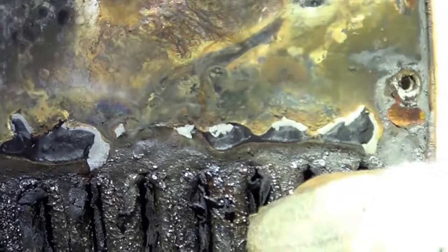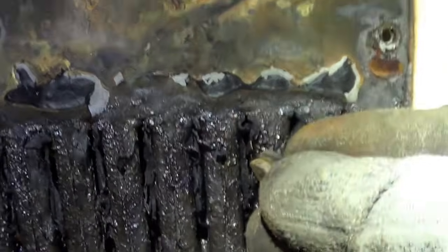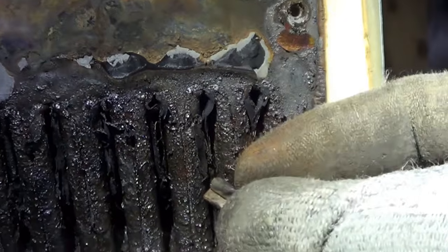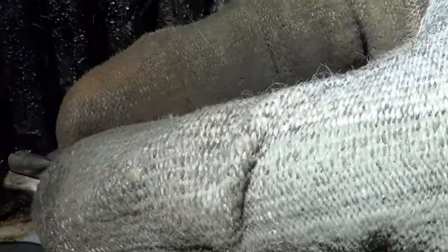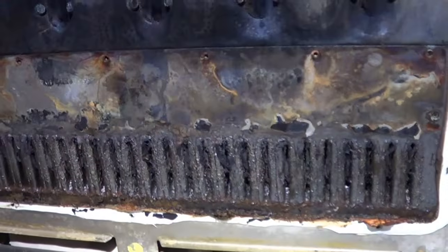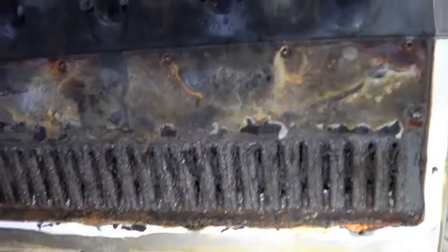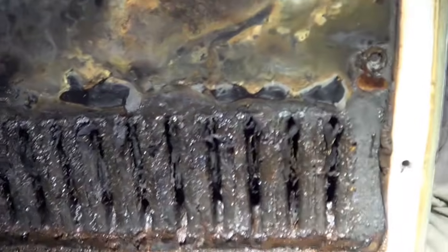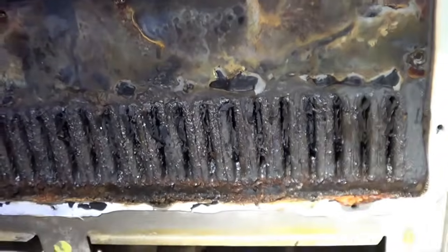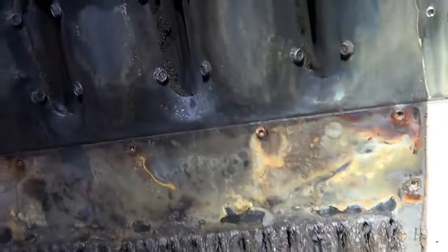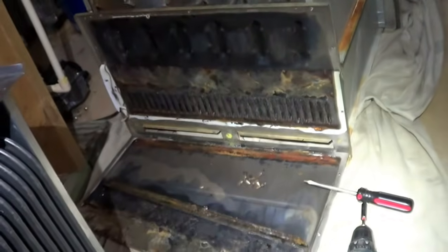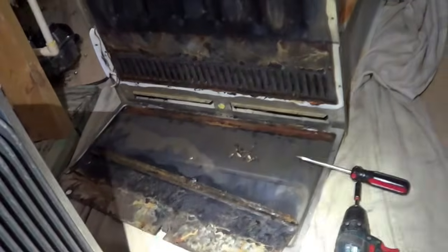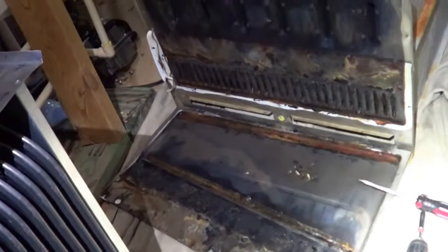So you can see it looks like more rust rather than soot. The pieces are flaking off. You can see they stick to the magnet. So on these Carrier type heat exchangers, you're not going to be cleaning those because it's not a soot that clogged up, it's an actual rust where the rust blocked it out. I mean, if you want to pull the whole heat exchanger, you might be able to clean it that way, but if you're pulling it, you might as well just replace it, because like I said, they did a bulletin where these are under warranty anyway.